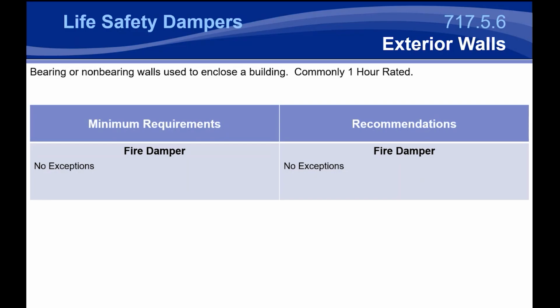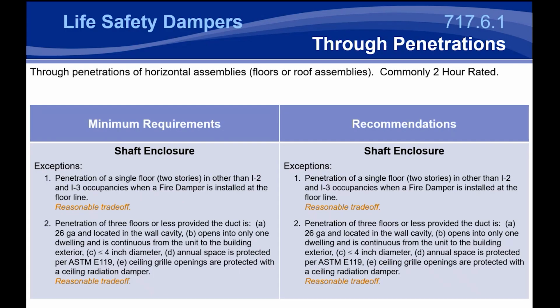This does introduce some issues in places like New York or Miami, where these exterior walls may need some requirement for protection, and there may be additional protection for louvers and things. That's typically when I recommend contacting us for support, because you may have multiple certifications that you have to balance in the same installation. Now, I talked about horizontally mounted corridor dampers in corridor ceilings.